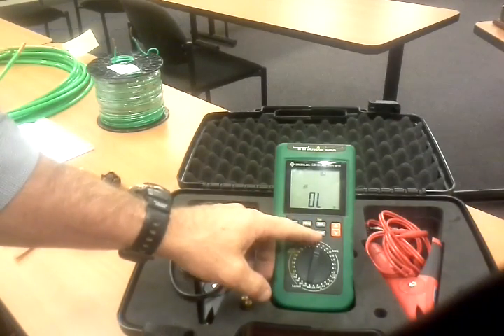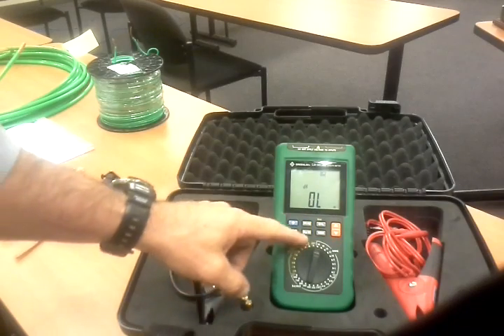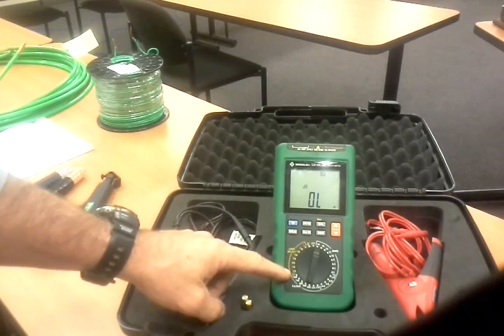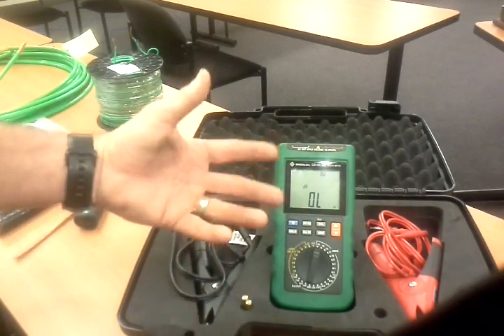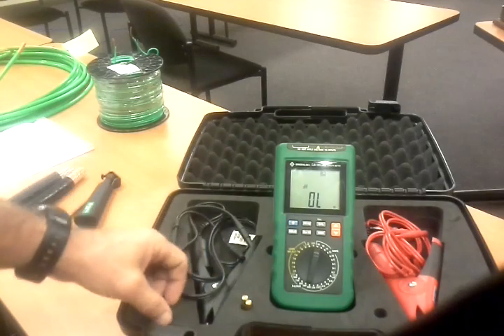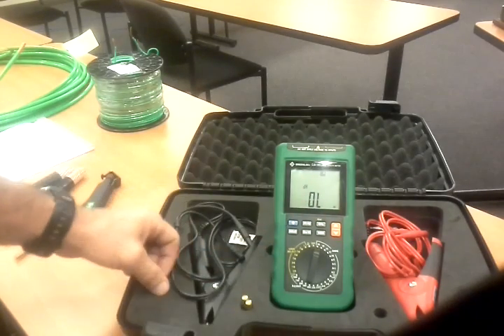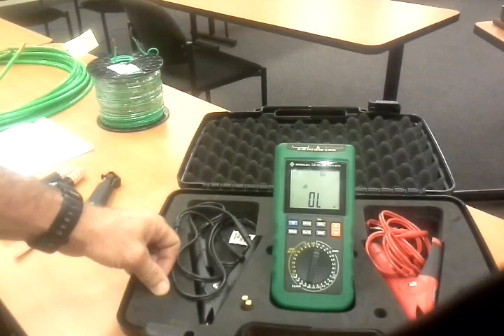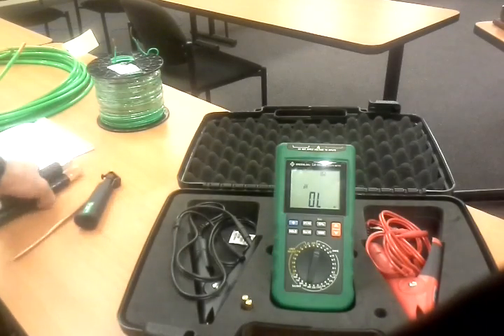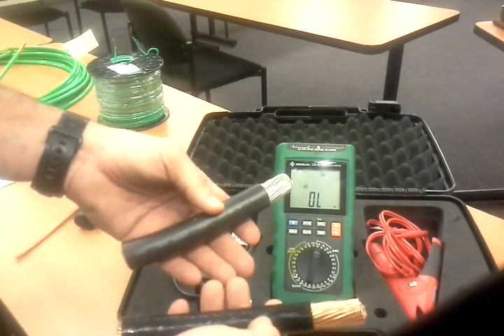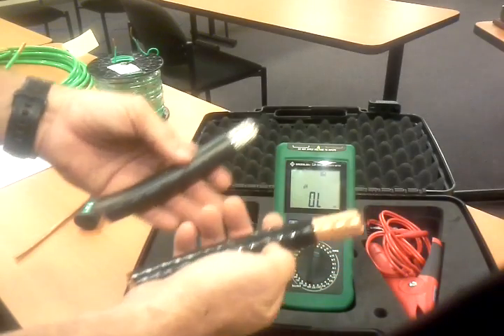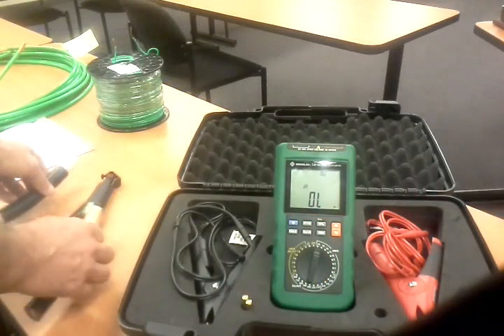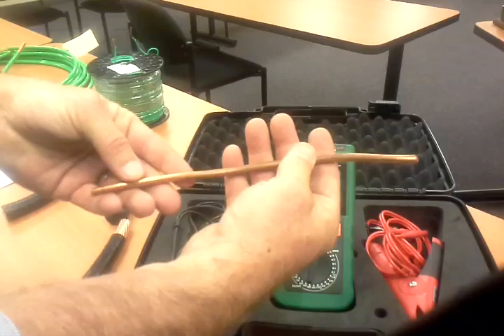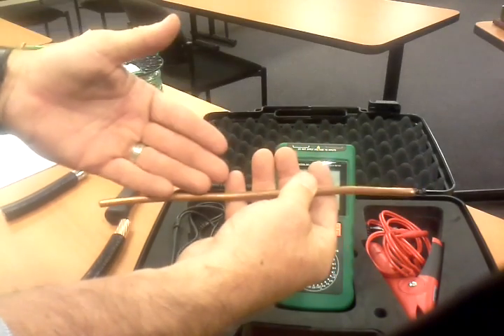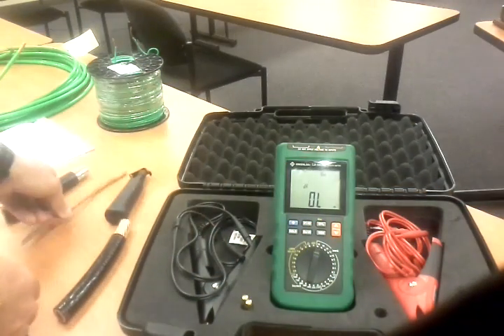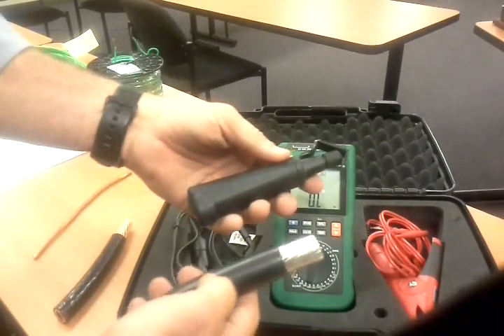It has a memory feature and an up and down arrow, which is used if you want to select a special size cable that you'd like to calibrate and measure. We'll show that later on. And then again, the calibration is used to set up and calibrate the meter each time it's turned on. The meter will measure 18 gauge to 1000 MCM copper, aluminum. It has to be insulated. You can't measure bare wire because it reads resistance and it all touches each other, so you won't get an accurate reading.